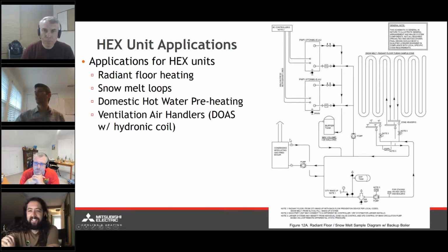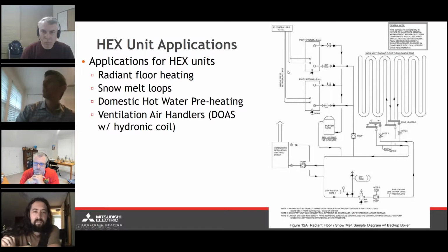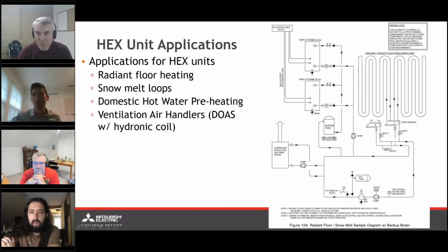Yes. So for this particular loop, we have 2 separate 6-ton HEXes. They're going to be twinned together, feeding into one single buffer tank. In this particular example, it's done in tandem with the modulating gas-fired boiler, but ultimately it's going to be served into multiple different zone headers. So exactly as you said, that's how we would deliver that to multiple zones.